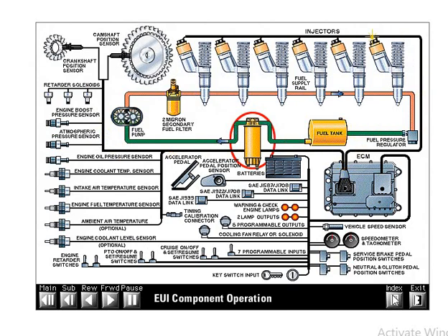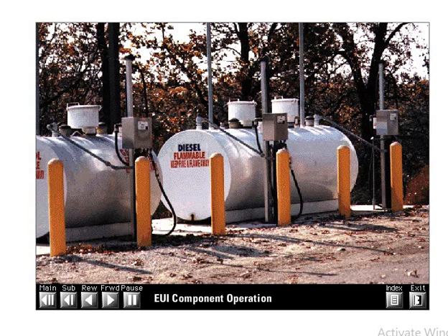Industrial or marine applications where large amounts of water may be in the fuel may have water separators in place of the primary fuel filter. The use and regular maintenance of a water separator is highly recommended where water contamination of fuel is a common problem. Water contamination is not usually as big a problem in on-highway truck applications that use fuel from reputable truck stops with very high fuel turnover rates. It is more of a problem for applications fueling out of stationary tanks with lower turnover rates.